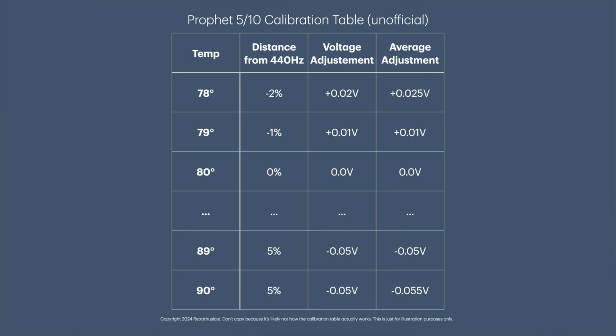Again, this is just my theory on how the Tune button works. There's probably a lot more that goes into this, such as deciding what voltage adjustment to use when the observed temperature is not in the calibration table. And what happens if you calibrate at the same temperature more than once. Hopefully, Sequential will share some details with its customers so we have a better understanding of what the calibration process actually does. Something else to keep in mind when pressing the Tune button.